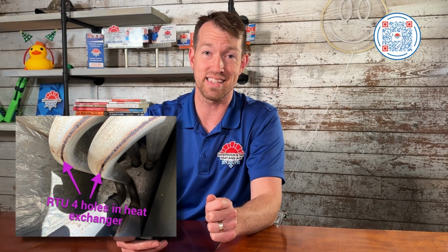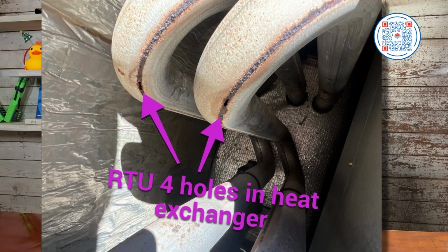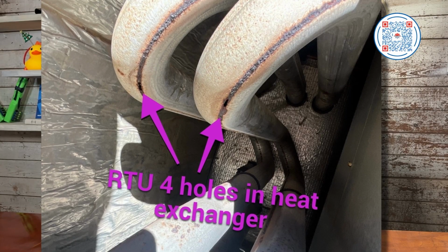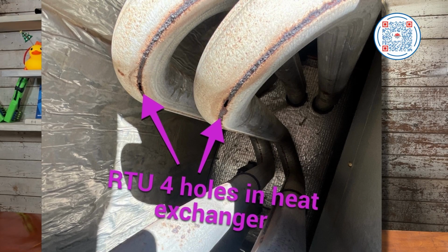And why that matters is carbon monoxide is going through those heat exchangers and is leaking out of those holes and coming into the conditioned air. So it's not good at all whenever you've got carbon monoxide mixing with the air that you're breathing in. The dangerous thing about carbon monoxide, if you didn't already know this, is that it doesn't have a smell, you can't taste it, and it can potentially be deadly in high enough levels in places that people live or work in. So anytime we see a heat exchanger that has holes in it, it's an automatic condemn of, at minimum, the heat exchanger, and at most, a system replacement scenario.